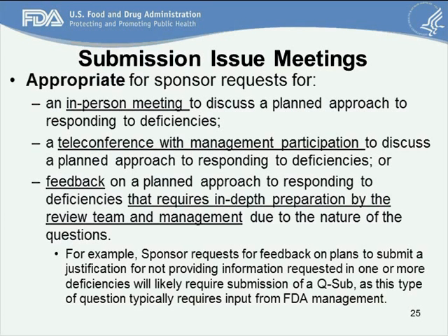to deficiencies. So what that means is if you had a 510K or a PMA or an IDE or any submission under review and it got put on hold with a deficiency letter, and you want to make sure that your approach to responding to that deficiency letter is going to be in the right ballpark, or you want FDA's feedback on some aspect of that response before you actually send it to the DCC, before you send in a 510K supplement or a PMA amendment, and you want a meeting to discuss that feedback, that's called a submission issue meeting.